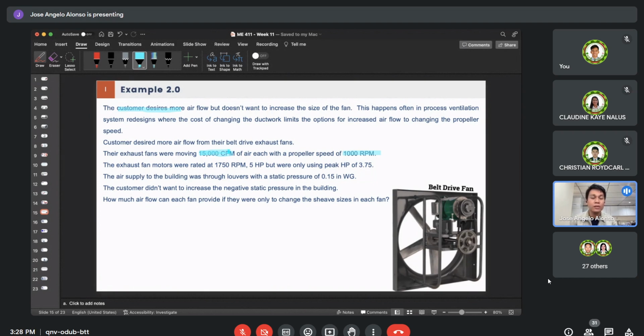The exhaust fan motors were rated at 1,750 RPM. And if we look, class, the rating of the motor is relatively much higher compared to the actual rotational speed of our fan, which is 1,000 RPM. So considering losses, the difference is still quite large. So we can still speed up our fan. Okay? But how do we do that?